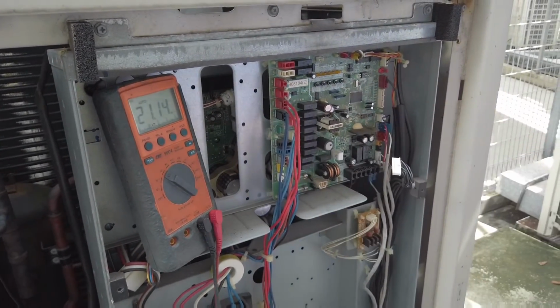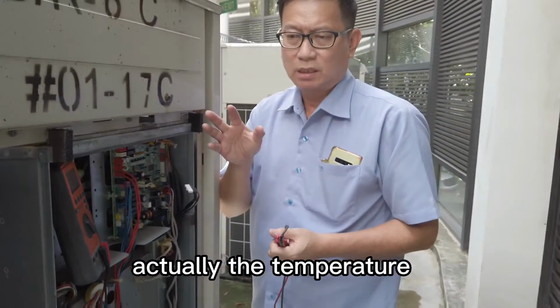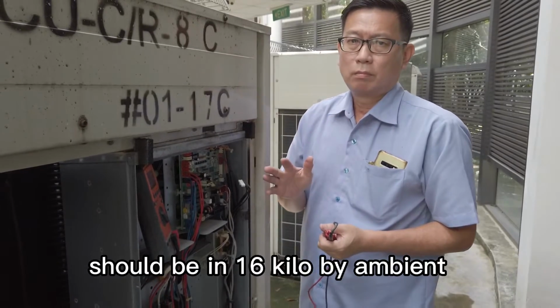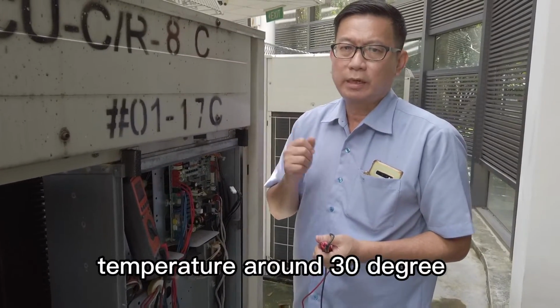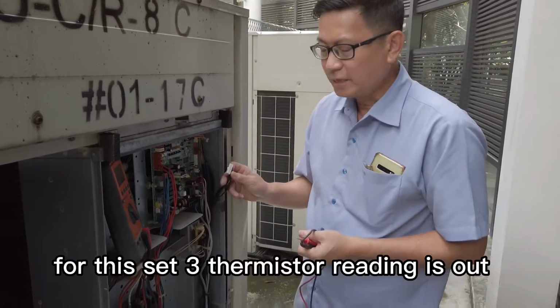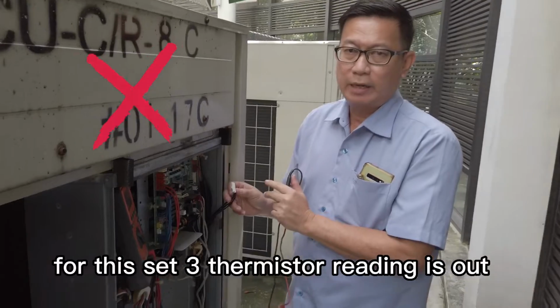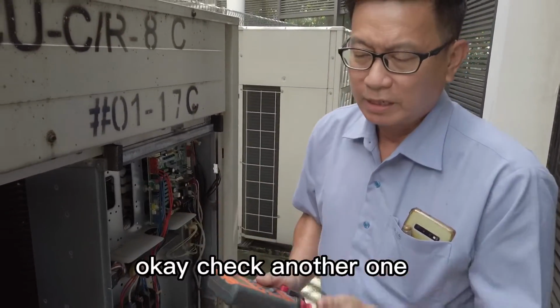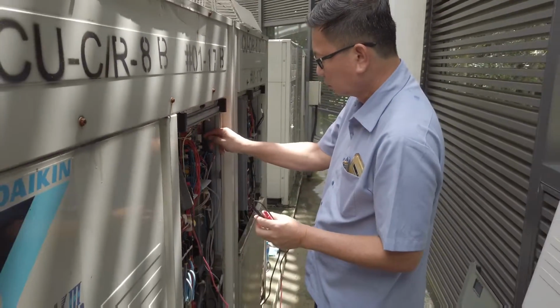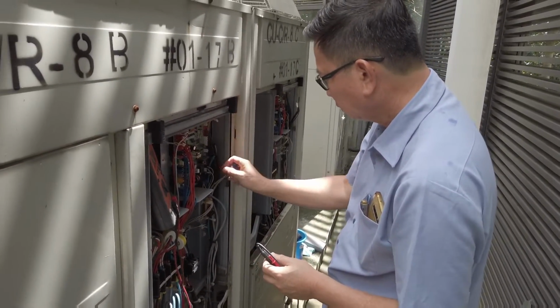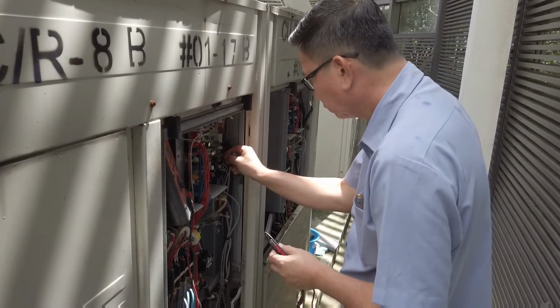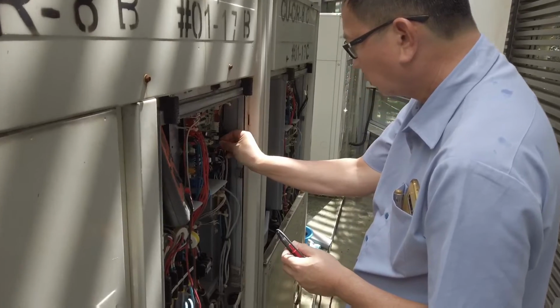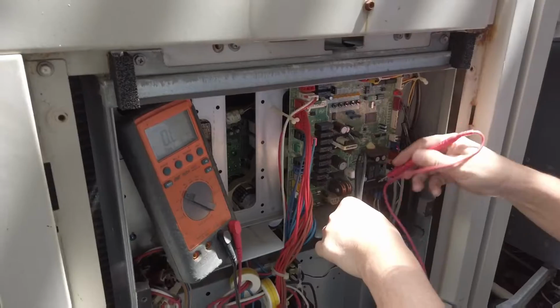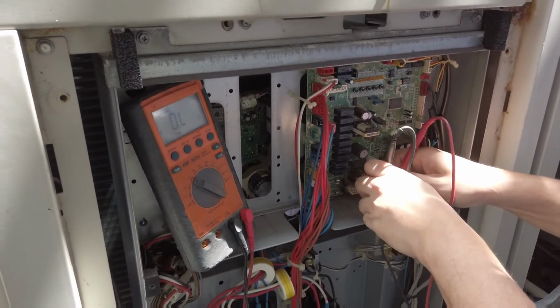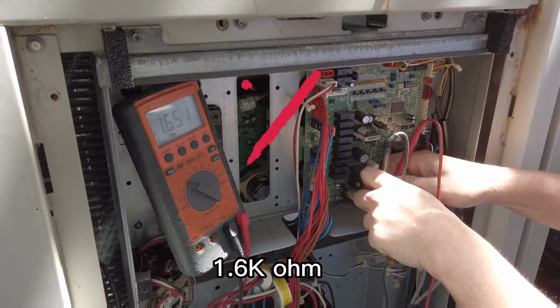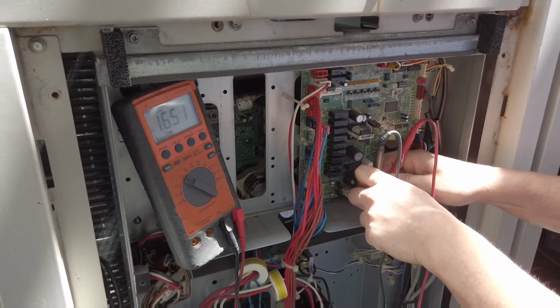21 kilo ohm. The aircon is not running actually. The reading should be 16 kilo ohm at an ambient temperature around 30 degrees. For this set, 3 thermistors, the reading is out. Okay, we check another one. This also out, 1.6 kilo ohm. Sabo, you take photo. You see 1.6. This also thermistor out.